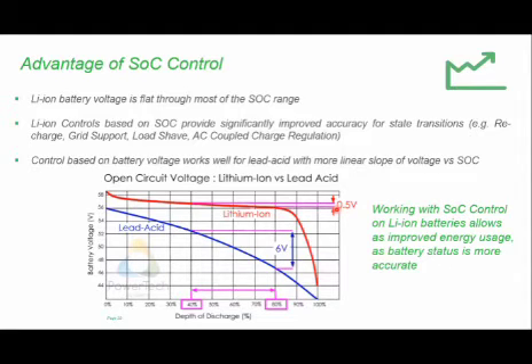So it can be confusing for a technical person, or anybody, and also confusing for the inverter. Where you have such small variations, how do you know when to transition from bulk to absorption to float? Those things can mess with the inverter's state of charge control when it comes to AC coupling, making it buggy to use AC coupled systems with lithium ion batteries if you're not careful.